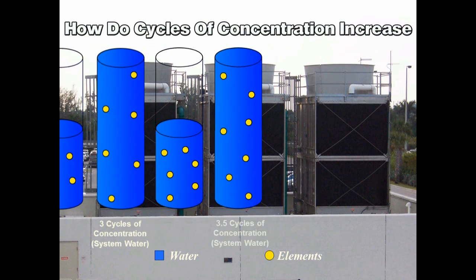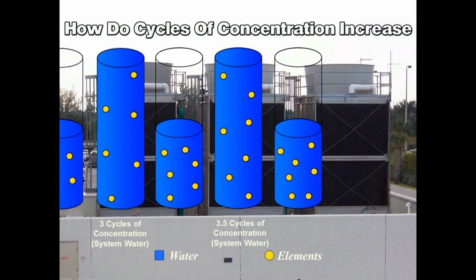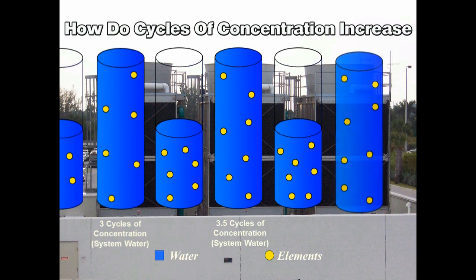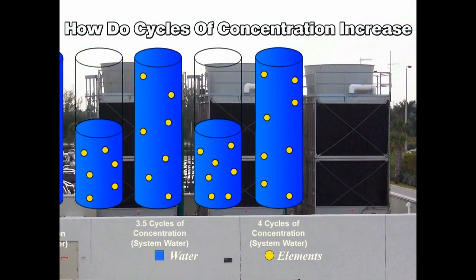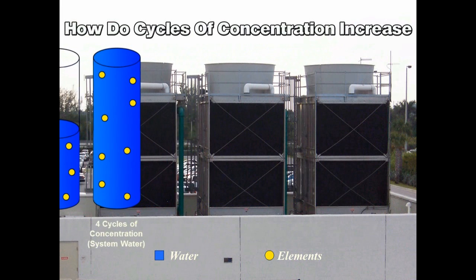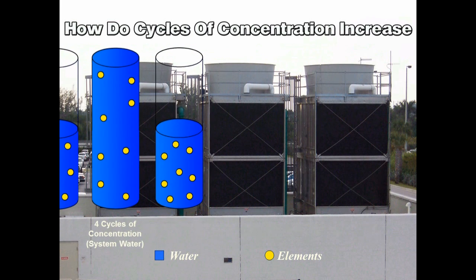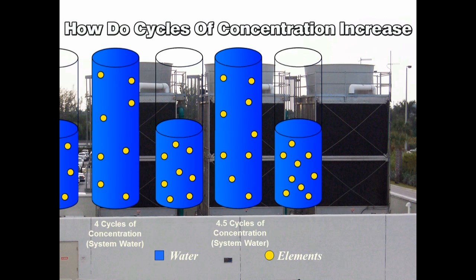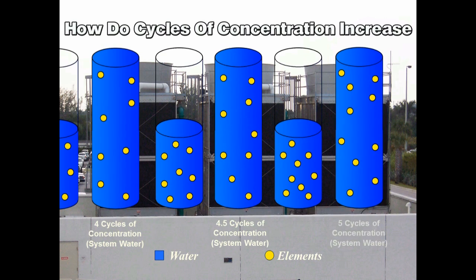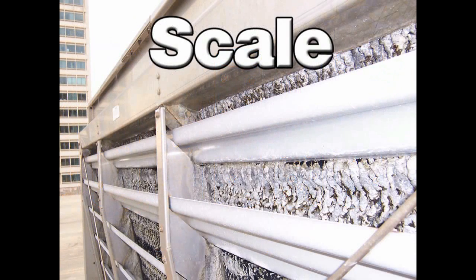Controlling cycles of concentration and the elements in water are extremely important to the operation of a cooling tower. When the elements in water concentrate to a level that exceeds the saturation point of the water, they fall out of the solution and form scale.